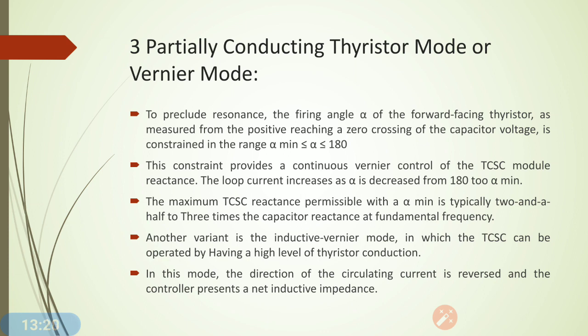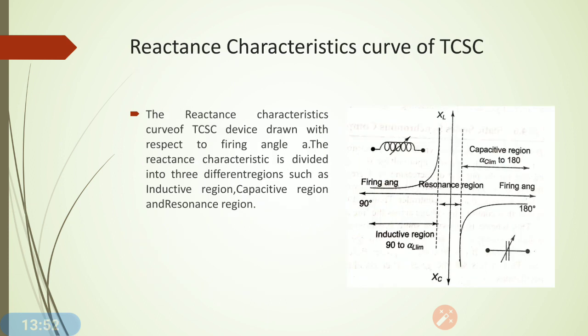The second variant of the thyristor vernier mode is the inductive vernier mode, in which the TCSC is operated with a high level of thyristor conduction. In this mode, the direction of the circulating current is reversed and the controller presents a net inductive impedance. So in the previous mode the TCSC behaves as a net capacitive impedance, whereas in this mode it behaves as a net inductive impedance.